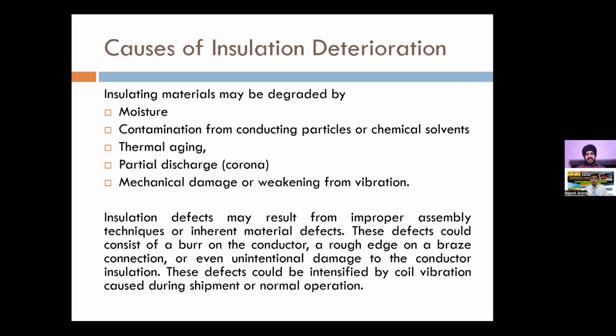Then if there is any partial discharge or corona inside, partial discharge is a very up and coming topic, and we are also very much into this partial discharge, which I will be covering very briefly in our subsequent slides also. Then if there is any mechanical damage or weakening from the vibration, it can also cause imbalance in the insulation, which can cause deterioration. So these insulation defects will cause the material defect and will ultimately lead to the failure of the winding of the transformer. But we need to identify what was the root cause of the insulation deterioration. So that is very important.